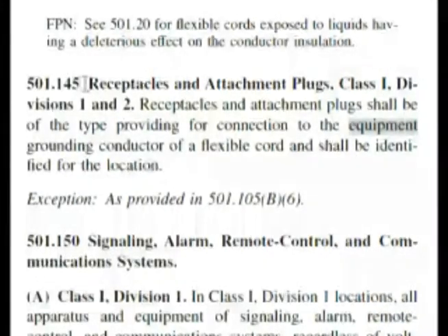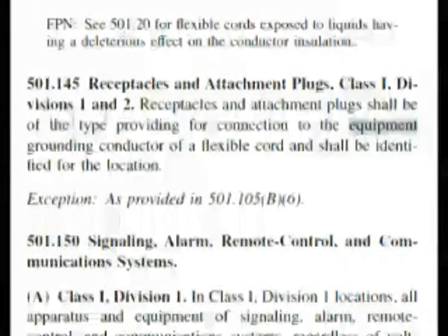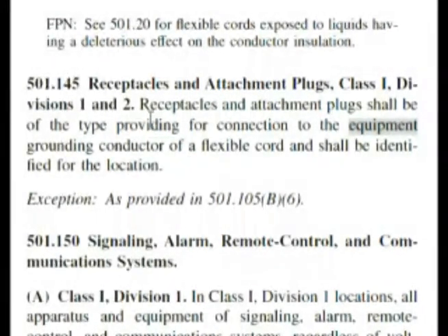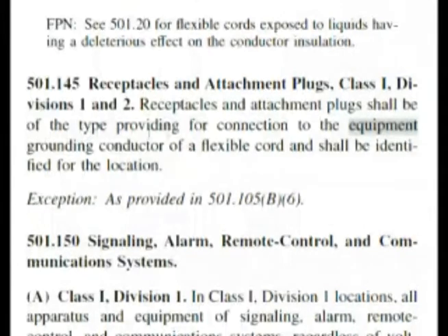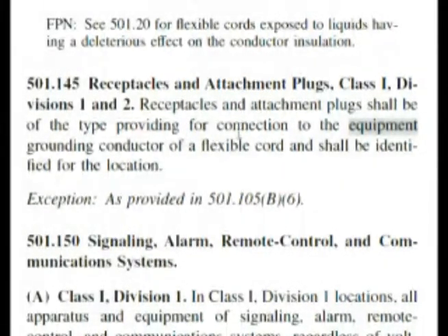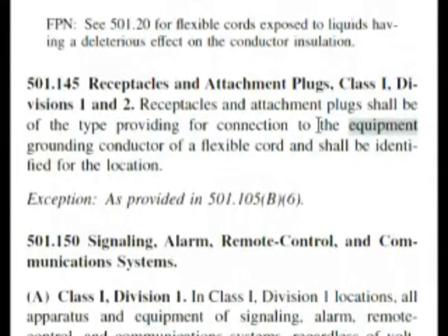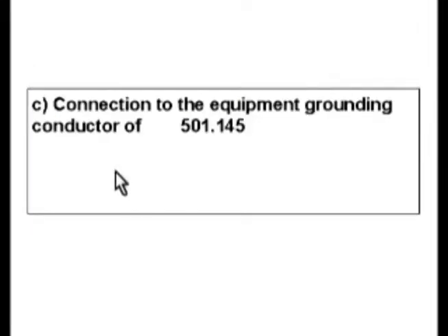Here we are in 501.145 — Receptacles and attachment plugs, Class 1, Divisions 1 and 2. This gets almost word for word in our question. Receptacles and attachment plugs shall be of the type providing for — and here's where our blank came in — connection to the equipment grounding conductor of a flexible cord. This is one of our answers, and that is choice C in our exam.